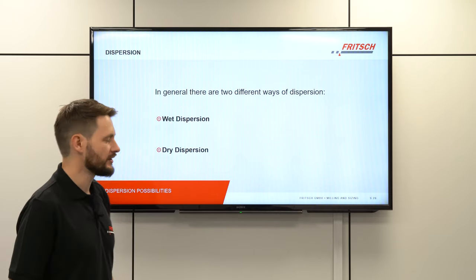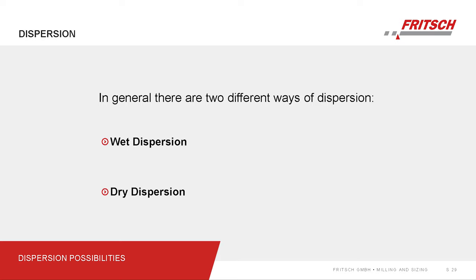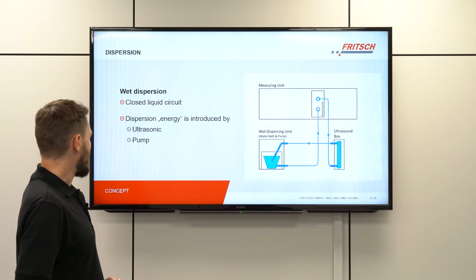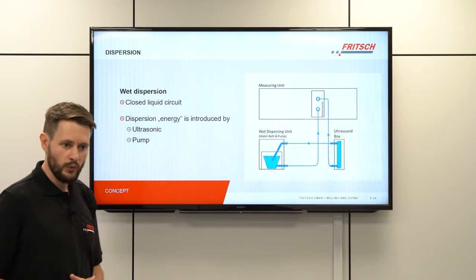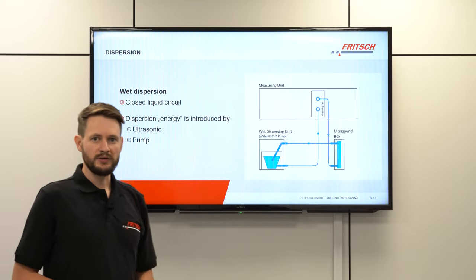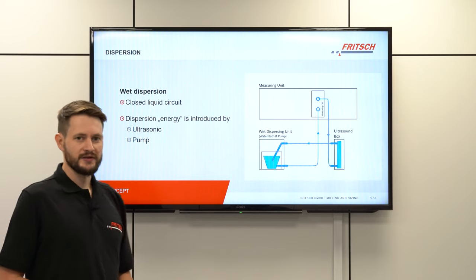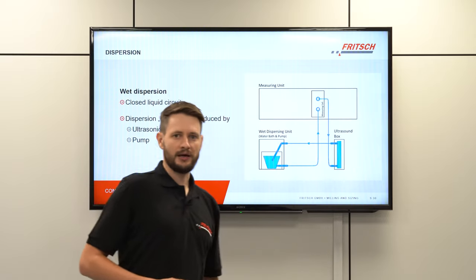There are two different ways of dispersing a sample: wet dispersion, which we've already shown, and dry dispersion. With wet dispersion we have a closed liquid circuit where our dispersion with the sample material flows and repeatedly passes through the measuring cell to be measured by the laser. The energy introduced to properly disperse the sample and minimize preparation error is the ultrasonic applied in the ultrasonic box, plus the pump which circulates the liquid through the system.